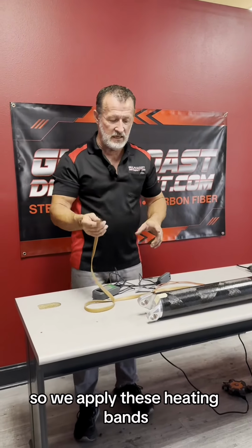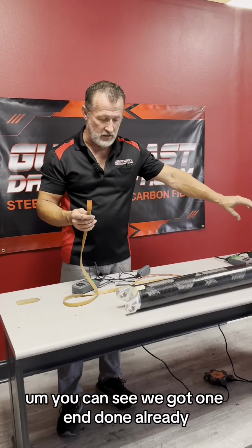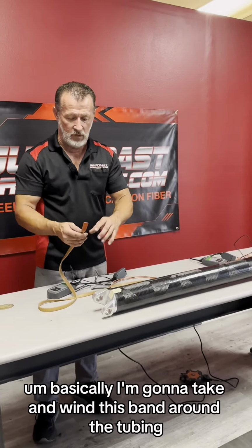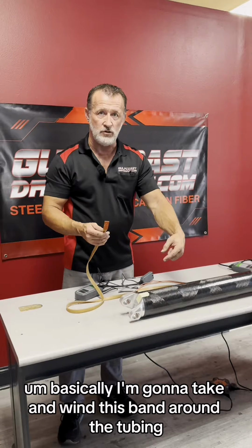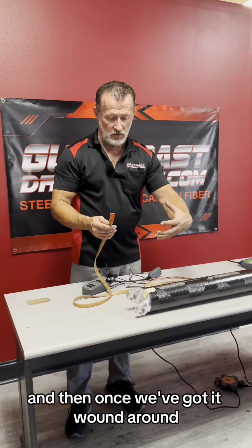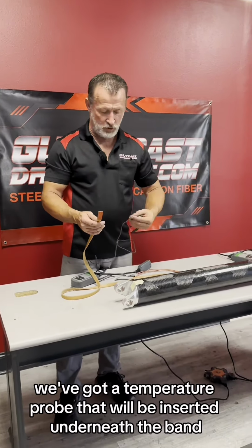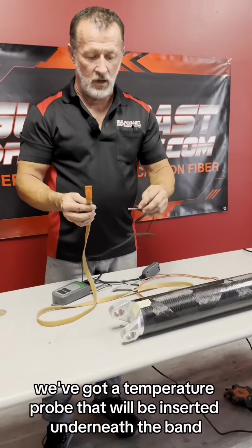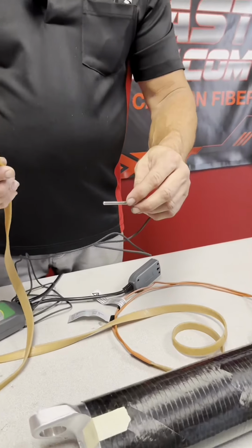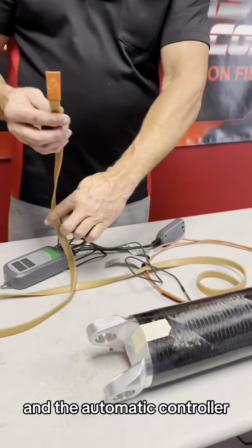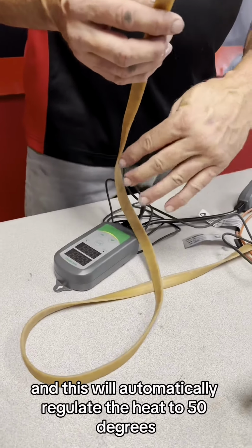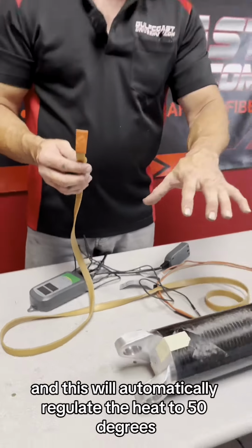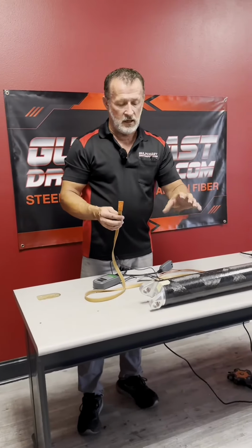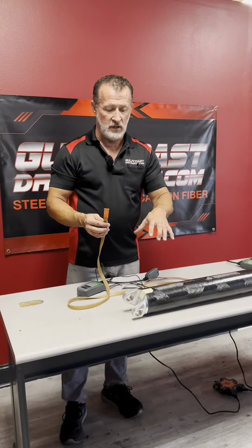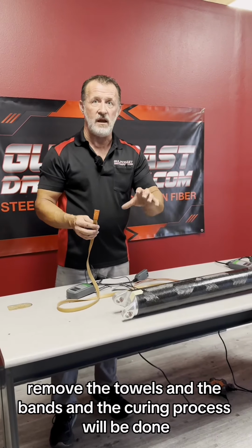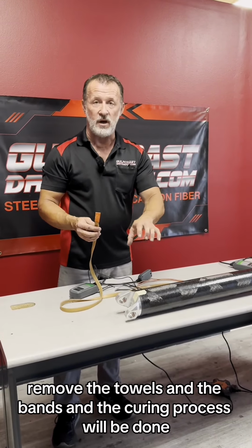So we apply these heating bands. You can see we've got one end done already. I'm going to wind this band around the tubing, and once it's wound around, we've got a temperature probe that'll be inserted underneath the band. The automatic controller has the temperature set, and it will automatically regulate the heat to 50 degrees for 2 hours. Then we remove the towels and bands, and the curing process will be done.